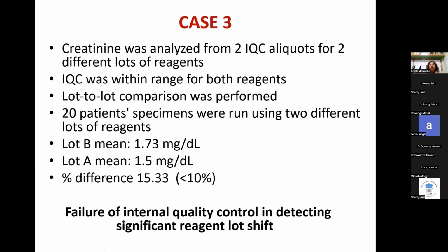Now I'll talk about a third scenario. This scenario was that lot to lot verification was done. There were two new lots of creatinine reagents. So they were analyzed and two IQC aliquots were taken for them to check the controls. When the controls were checked, both were coming all right. So a lot to lot comparison was performed.